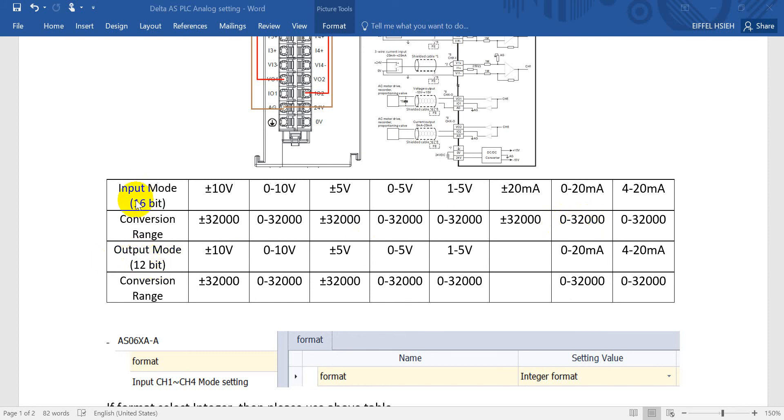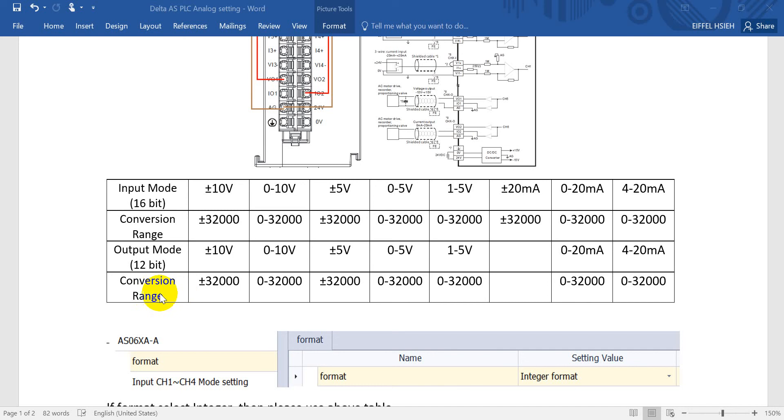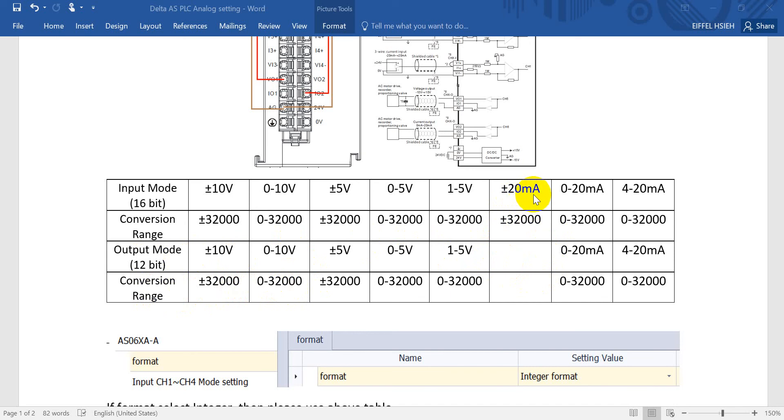We have to emphasize the input module hardware resolution is 16 bit. However, for the output we have only 12 bit. But you can see the conversion range still becomes plus minus 32K or 0 to 32K. From this table you can find for the output mode we don't have plus minus 20 milliamp, but the rest modes we support.